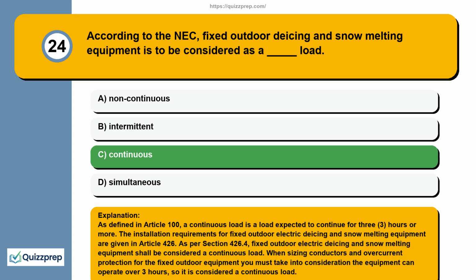As defined in Article 100, a continuous load is a load expected to continue for 3 hours or more. The installation requirements for fixed outdoor electric deicing and snow melting equipment are given in Article 426. As per Section 426.4, fixed outdoor electric deicing and snow melting equipment shall be considered a continuous load. When sizing conductors and overcurrent protection for the fixed outdoor equipment, you must take into consideration the equipment can operate over 3 hours, so it is considered a continuous load.